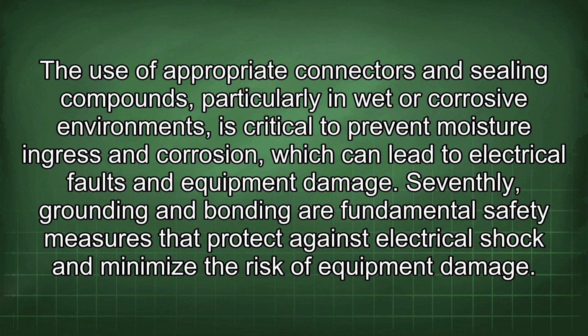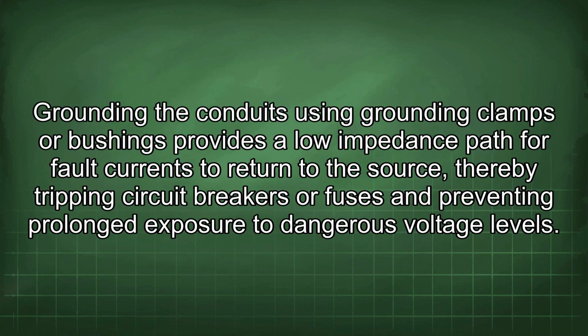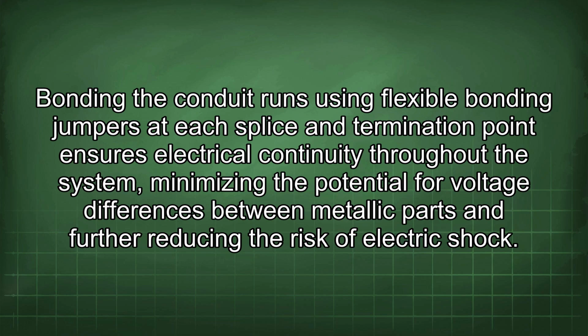Seventhly, grounding and bonding are fundamental safety measures that protect against electrical shock and minimize the risk of equipment damage. Grounding the conduits using grounding clamps or bushings provides a low impedance path for fault currents to return to the source, thereby tripping circuit breakers or fuses and preventing prolonged exposure to dangerous voltage levels. Bonding the conduit runs using flexible bonding jumpers at each splice and termination point ensures electrical continuity throughout the system, minimizing the potential for voltage differences between metallic parts and further reducing the risk of electric shock.